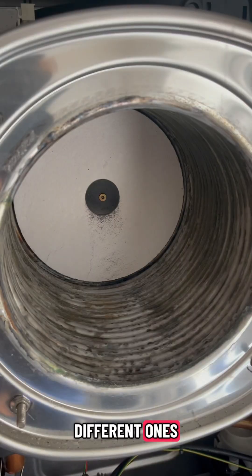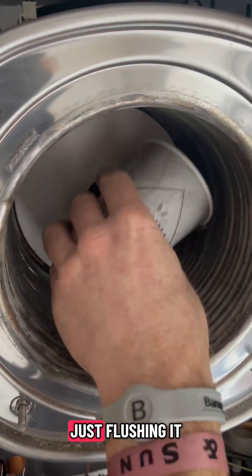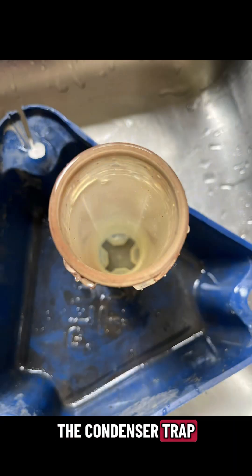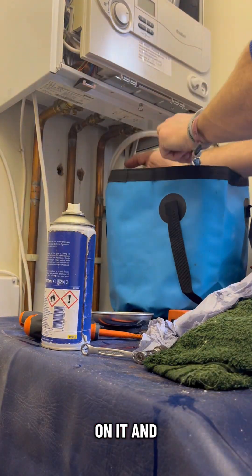It doesn't look too bad to be honest, but we said the full service so we're going to clean it out. Using soft brushes - different ones - making sure it's all nice and clean, all the channels are clean. Then flushing it out with water, removing the condensate trap and cleaning it out with silicone.